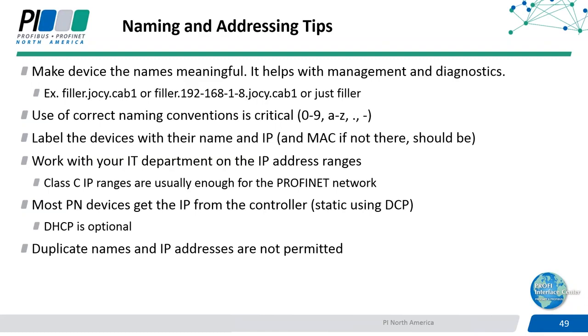For example, if I've got a filling machine, I could call it just 'filler.' That gives me a little information—it's the filling machine—but I could expand on that. I could say it's the filler in 'Jocy,' since I'm in Johnson City, and it's in cabinet 1. Or I could get more extravagant and put the IP address as part of the name. Now I've got the name of the device, the IP address, and where it's located exactly in the name. So if I get a diagnostic event, it would pop up in the diagnostic buffer of the PLC, showing the error coming from this filling machine at this location, giving us useful information.